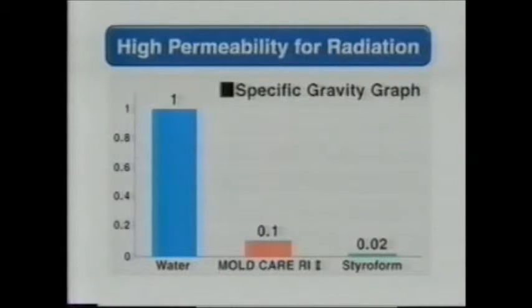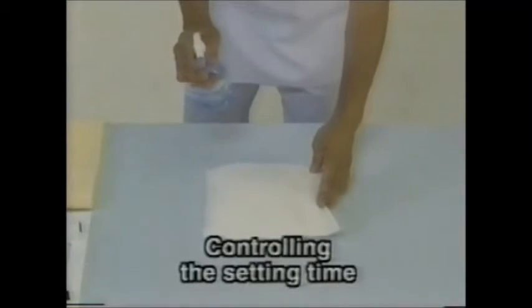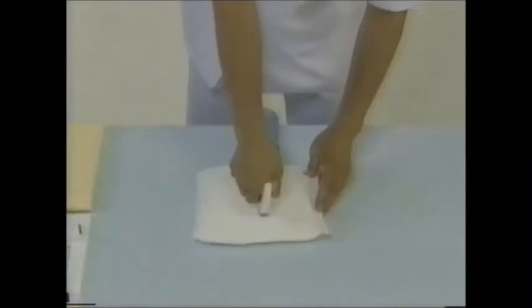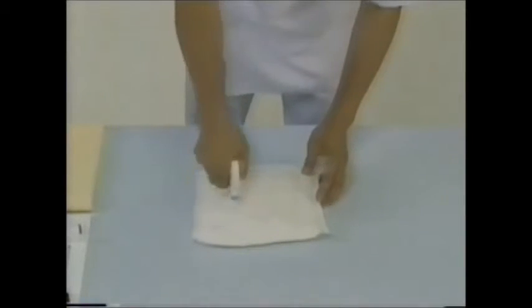Since Moldcare RI-II has a low specific gravity of 0.1 with a CT value of less than minus 800, the device can be used in treatment with a CT simulator. Production time of the Moldcare RI-II patient immobilizing brace can be controlled by adjusting the temperature and quantity of water, enabling the user to mold the device according to the body shape of each patient.